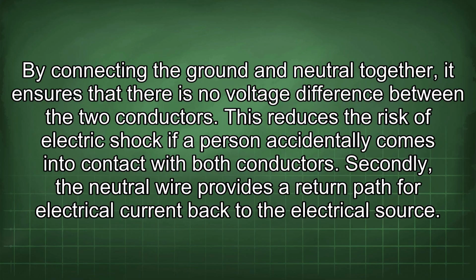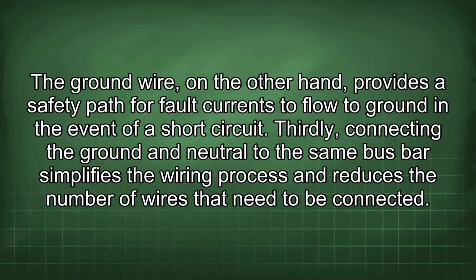Secondly, the neutral wire provides a return path for electrical current back to the electrical source. The ground wire, on the other hand, provides a safety path for fault currents to flow to ground in the event of a short circuit.